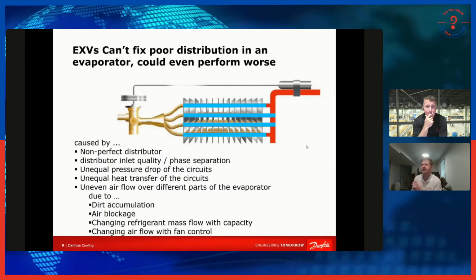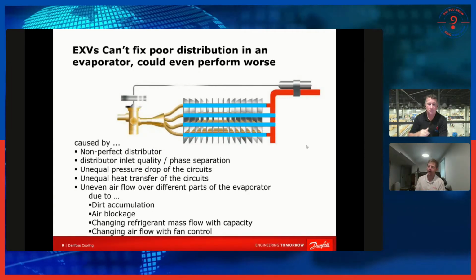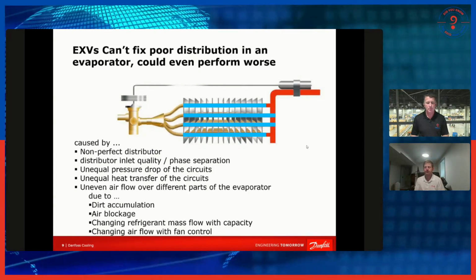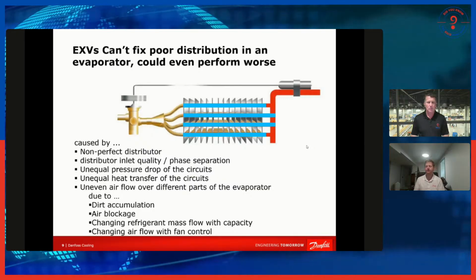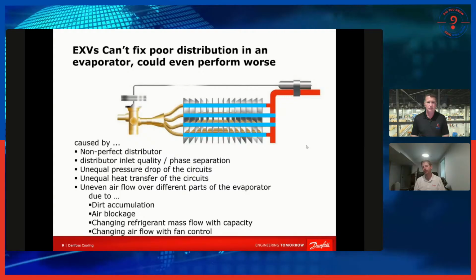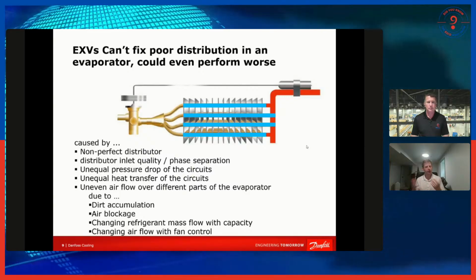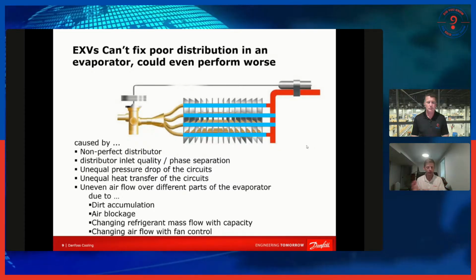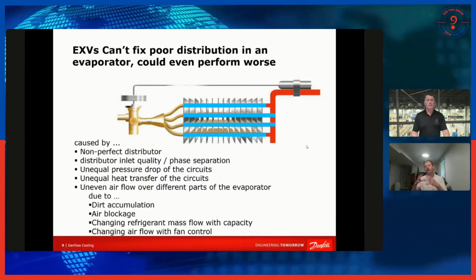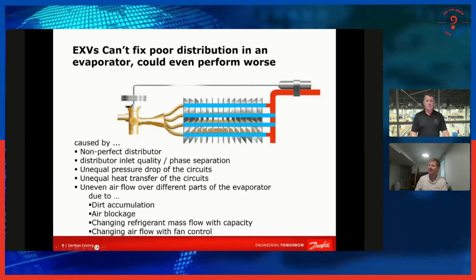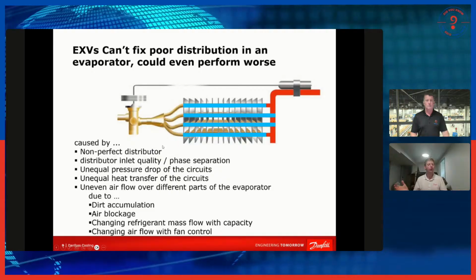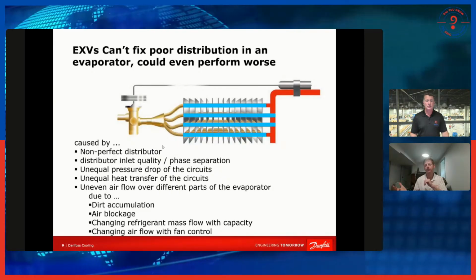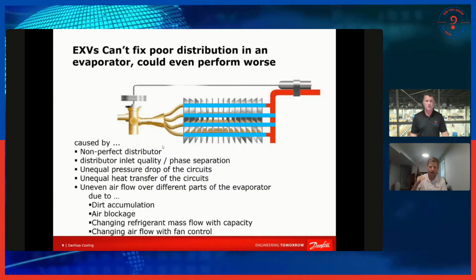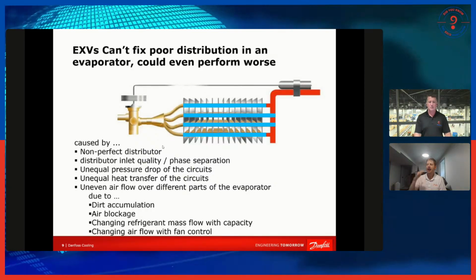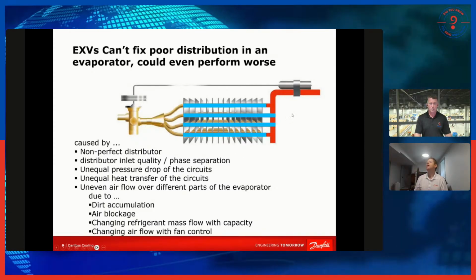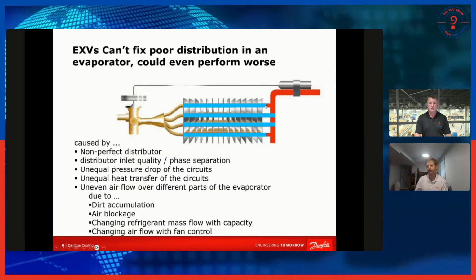Another thing that EXVs can't do is fix poor distribution in an evaporator. If you have poor distribution, that can create big problems and lead to hunting. And when I say unequal distribution, I mean this in two different ways, and both have the same basic effects. If you have a distributor that doesn't equally distribute refrigerant to each one of the circuits in your evaporator, or your ductwork is set up in a way so that you're not getting even airflow across all the circuits in your coil, you're going to have refrigerant evaporating off at different rates. And then you'll have certain circuits that can flood back while other circuits are starving.